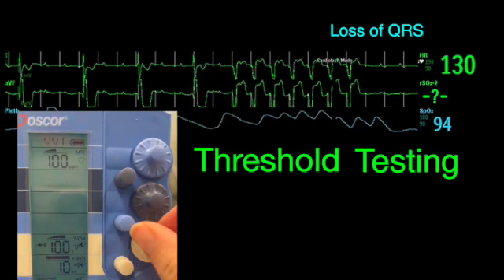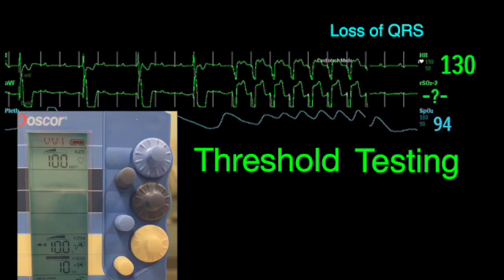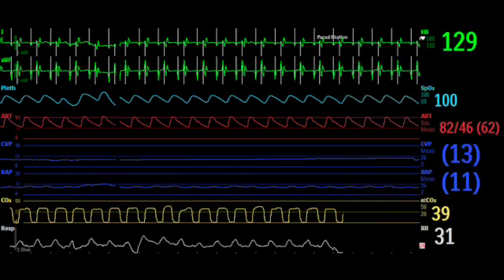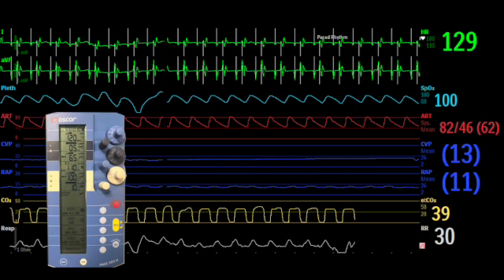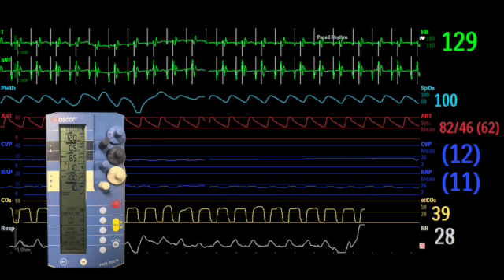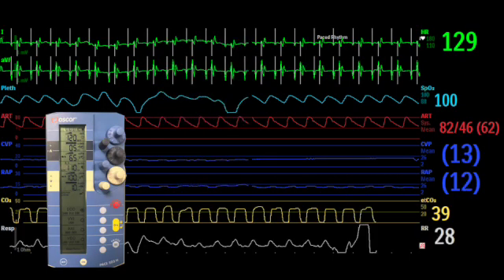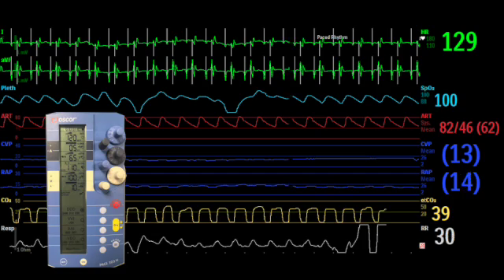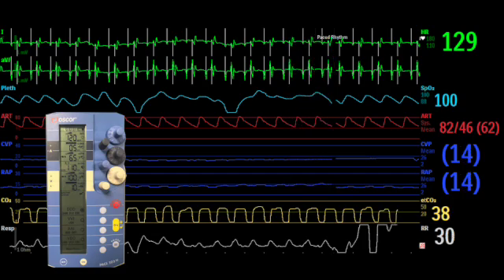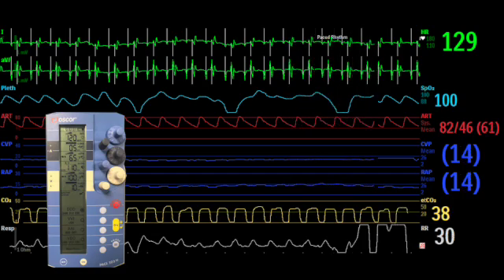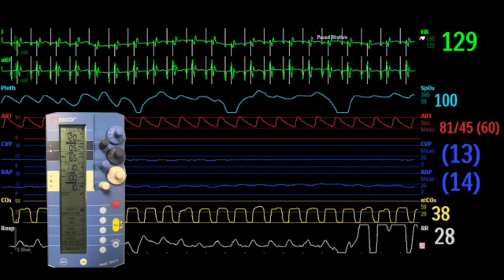Setting the pacemaker output right above the threshold probably isn't a good idea, as it doesn't give you a margin of safety should the pacer wires become less functional in the middle of the night. The rule I was taught is that the output should be at least two times the threshold. However, when the wires are new, the threshold may be very low, so the lowest I ever set the output is five milliamps.